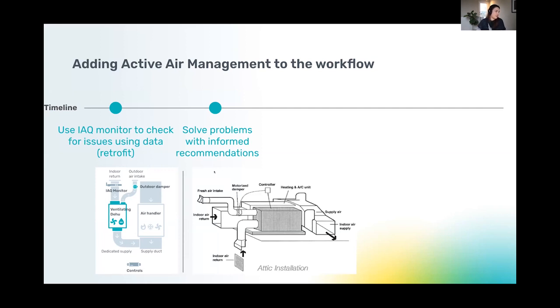Yeah, so here's just a quick overview. I know we talked about it earlier with the ventilating dehu and damper, but just a couple of ways to visualize how this equipment might be set up, especially, as we mentioned before, we're specializing in the Southeast. So a lot of the HVAC systems here are just installed in a closet, and they don't actually have a proper return duct. It's just a grill and then equipment right away. So there's no actual place to insert the monitoring system, which is why we would install it in the return of a ventilating dehumidifier.